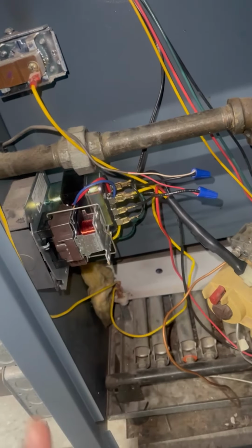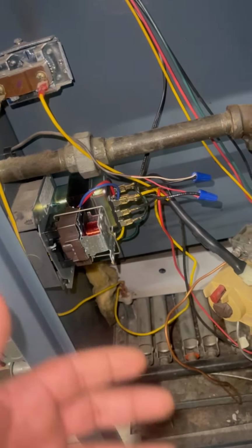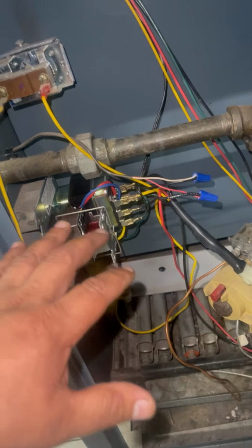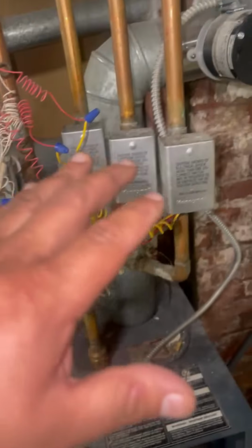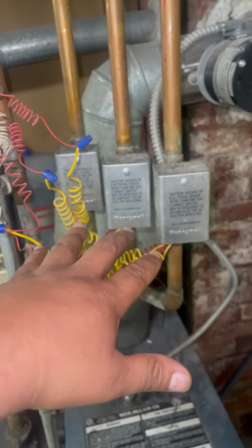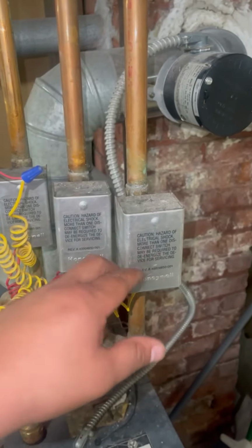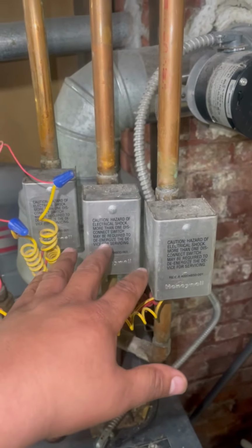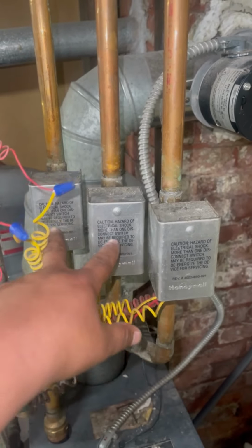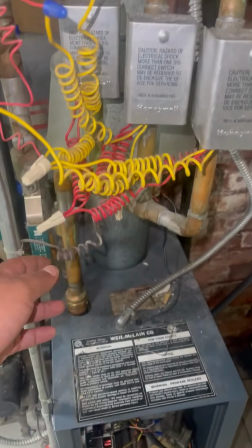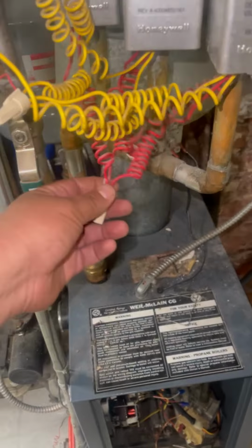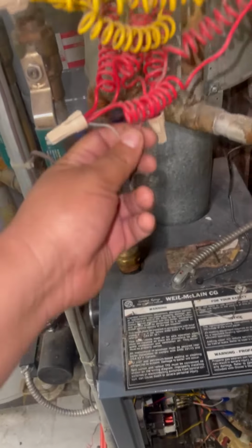But what I'm trying to get to you guys is that whenever you're doing troubleshooting, you want to isolate what could go bad. So the first thing I isolated was the actual zone valves. I made sure they're getting 24 volts. So they were getting 24 volts because these zone valves are normally in a closed position. And when I get 24 volts, they open. These 2 were open. The end switch was making, which is right here. This is one. I'm sorry. Yep. This is the end switch right here.